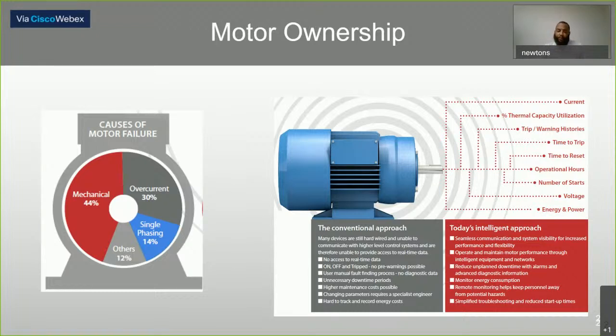So with your smart motor control devices, with them being networked, you now have the availability and the visibility to monitor and trend your current, thermal capacity utilization, your trips or different types of warnings, how much time has passed since you had a trip, how long your motor has been running, how many starts your motor has had, and what the voltage looks like. And for those looking to track the dollars being spent to turn these machines, you can monitor your energy and your power to keep your utility honest.